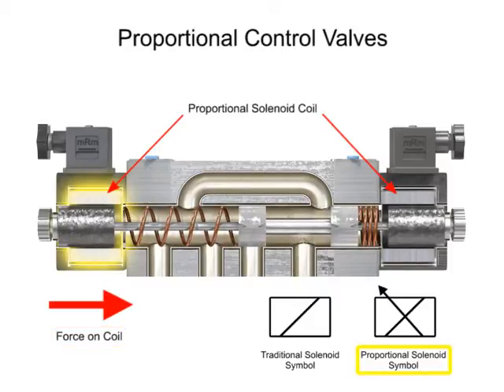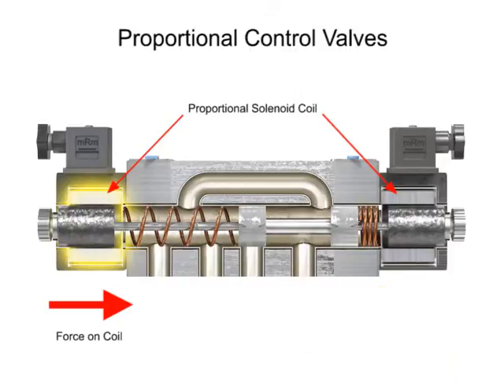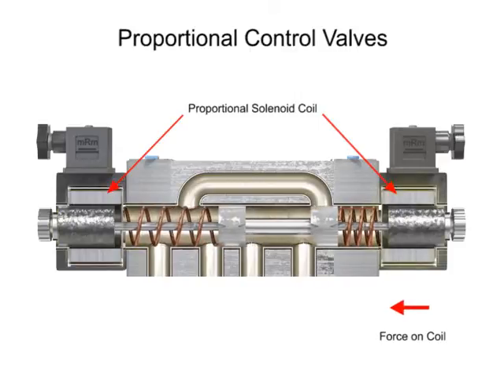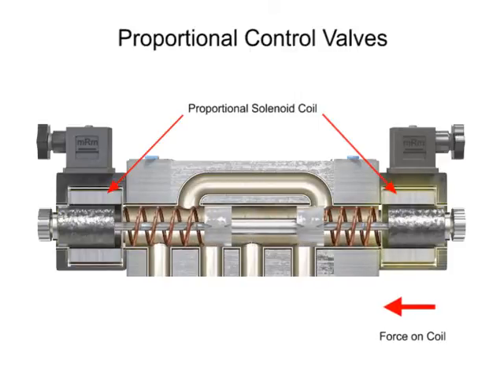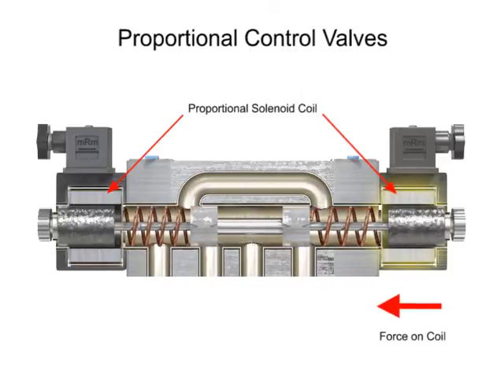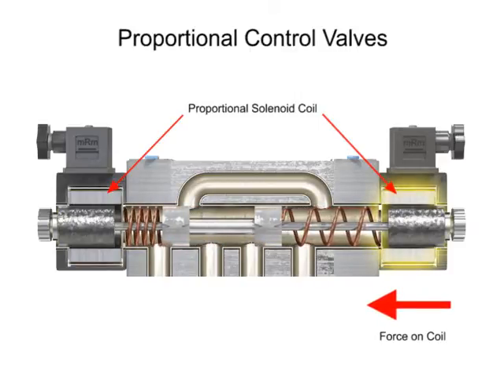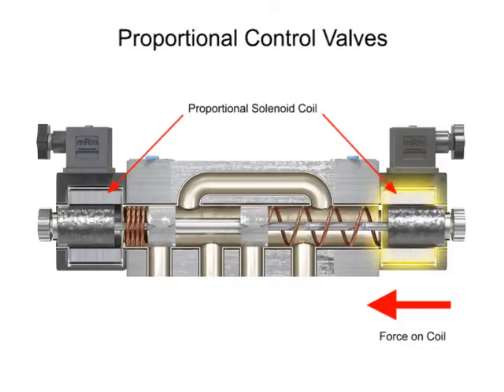The graphic symbol for this type of solenoid is a slash in the operator box with a sloping arrow through the slash. With proportional valves, the spool can be shifted against the centering spring force to any distance up to full shift by varying voltage and current.